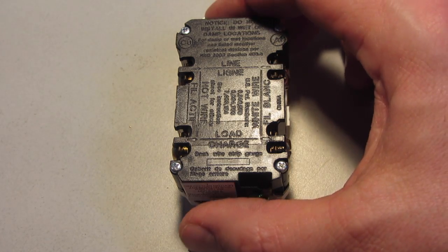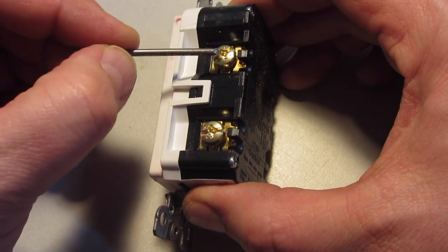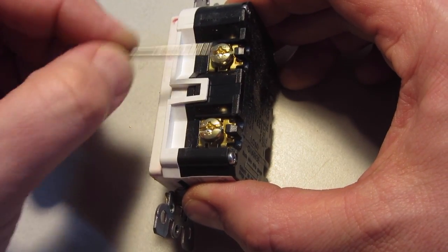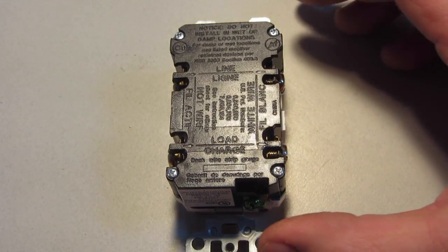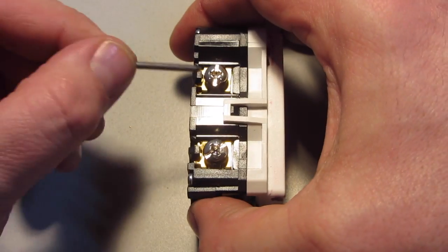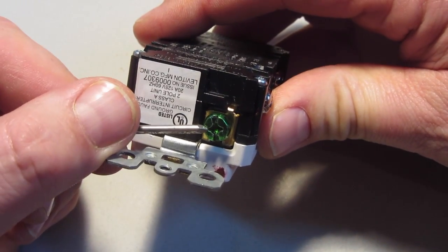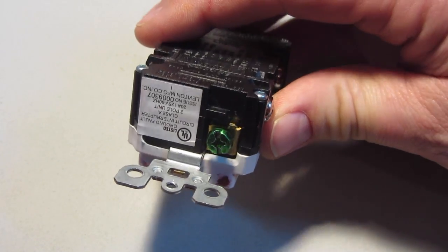The black wires, which are the hot wires, will be connected to the gold screws. The white wires, which are neutral wires, will be connected to the silver screws. There is also a green screw, which takes the ground wire.